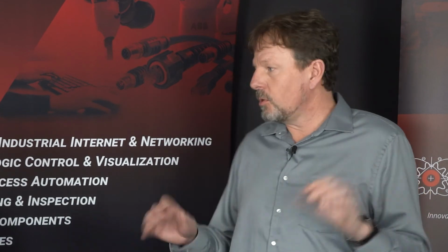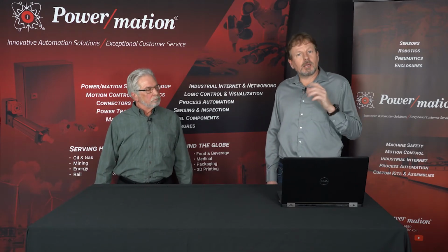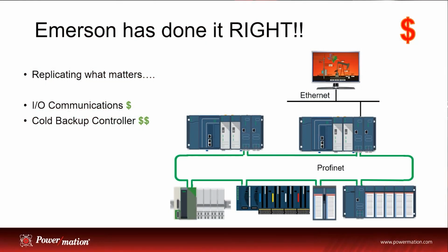Secondarily, a controller. Now, most people say, hey, what if that controller goes down? You should have one on the shelf. So now you take this controller, you purchase the controller, you stick it in a warehouse location someplace, and that becomes your backup. Well, as long as it's going to be sitting on premise, on your property, why not just install it in the control panel and have both controllers sitting there running all day long, and then if one of them fails, you move the cables over to the secondary one. Well, guess what? That's going to take time. And all the set points that were in controller number 1 need to be replicated into controller number 2. So even though you've got two controllers, that's what sometimes we call cold standby or a cold controller.